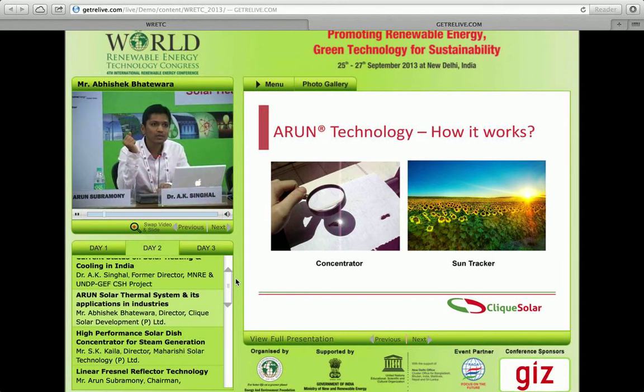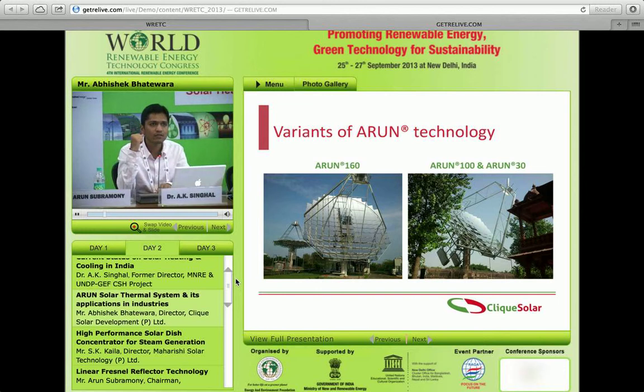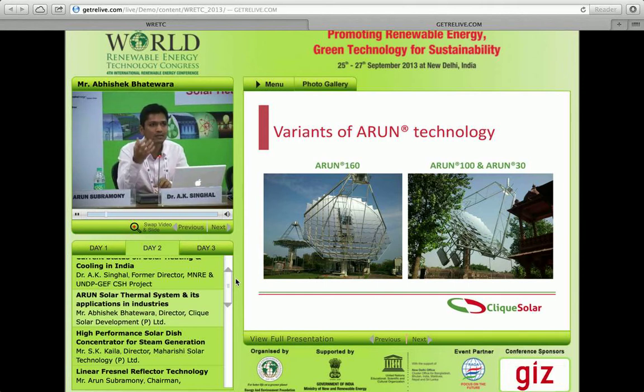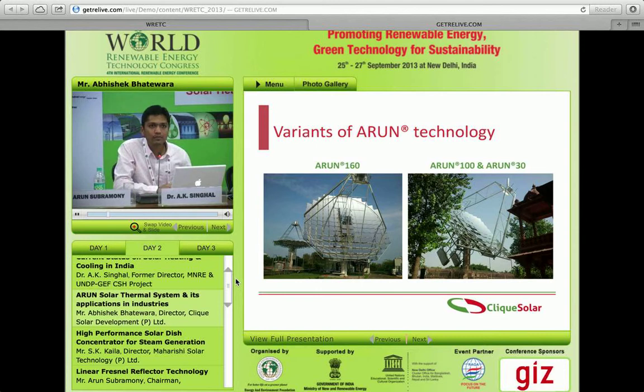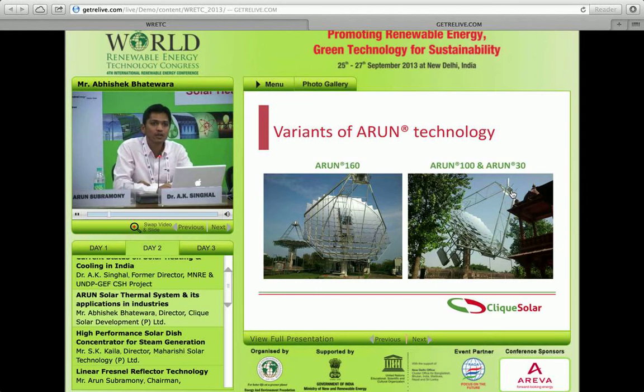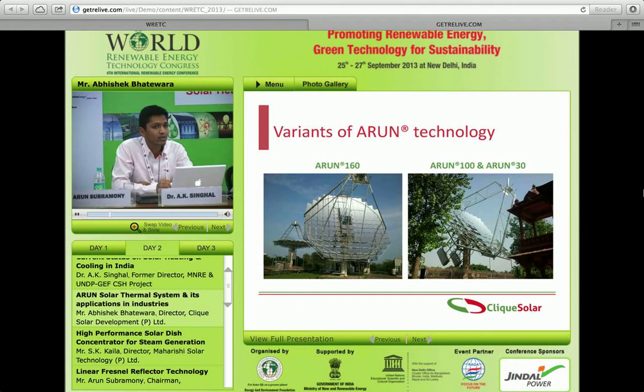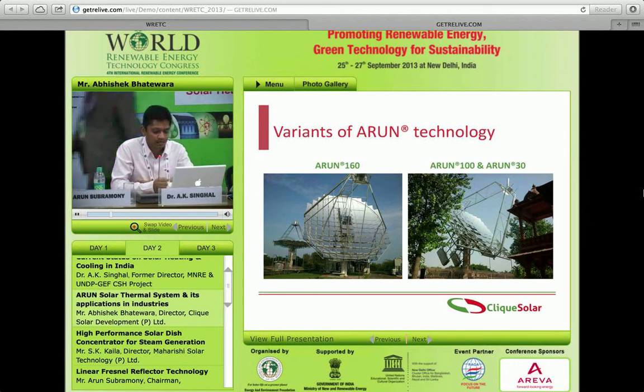This is how the Arun system looks. We have multiple variants: Arun 160, Arun 100, and Arun 30. The numbers represent the size of the collector area — the area on which sun rays fall. All sun rays falling on this collector area are focused on one particular point at the receiver. At this point, temperatures achieved are very high — if heat is not evacuated, it can reach 1500 degrees Celsius. But for usable energy, it can go up to 350 degrees Celsius, with concentration ratios of about 500x.